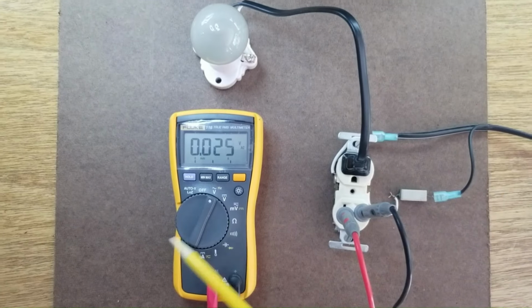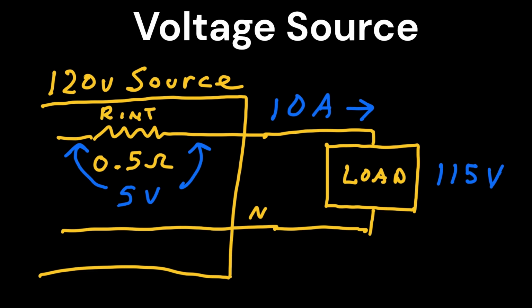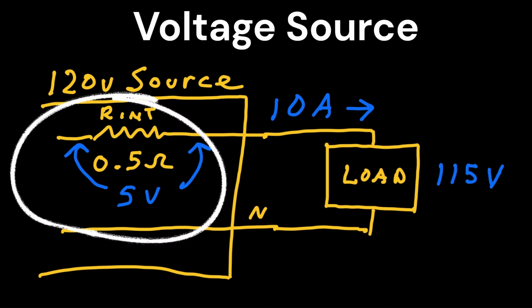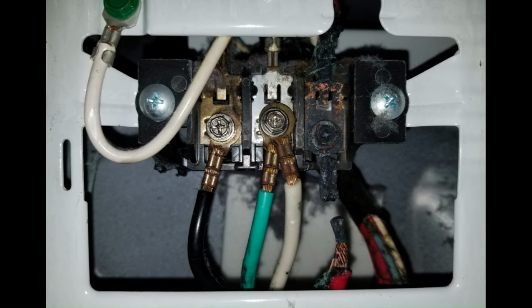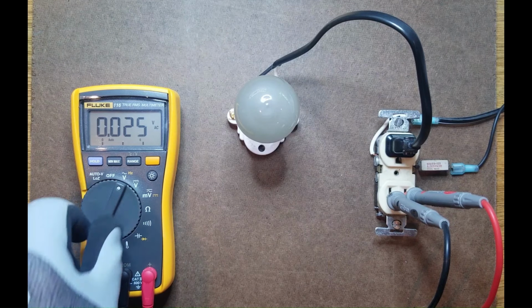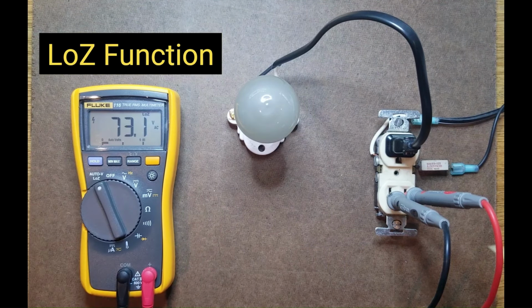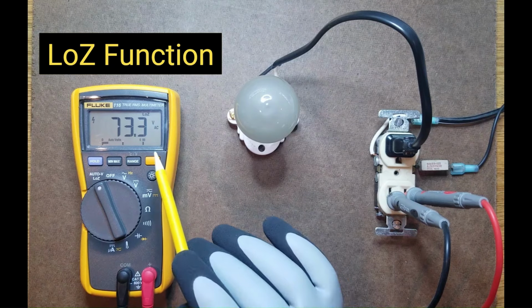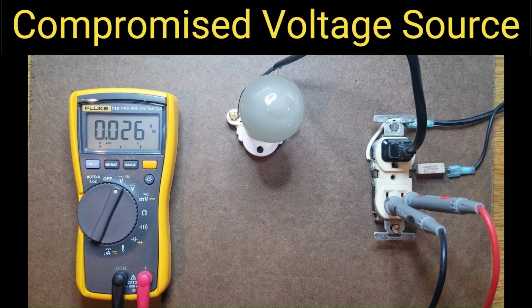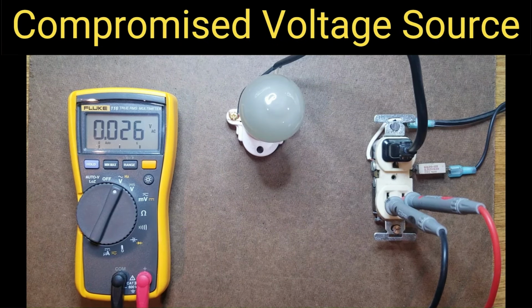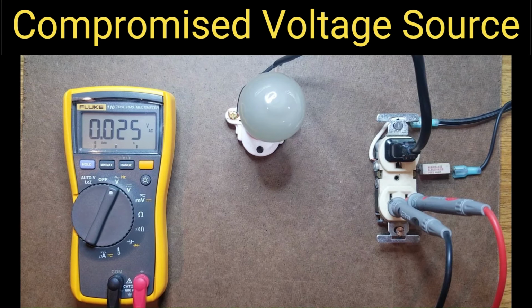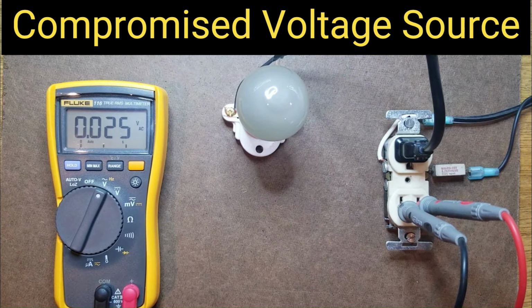In this video, you'll learn why this happens, how voltage sources work, why they have limitations, how loose connections can compromise them, and how you can use the LoZ function to reveal such problems. What we actually have here is a compromised voltage source, a situation that is quite common and often necessitates the use of a LoZ meter to detect.